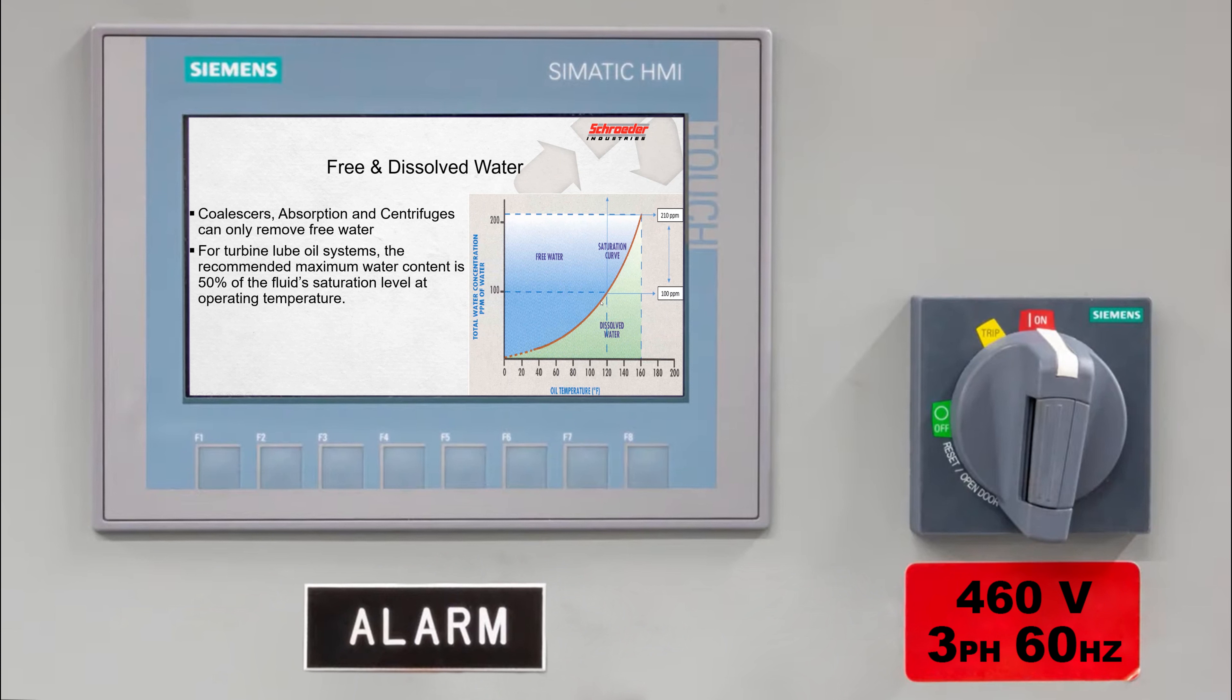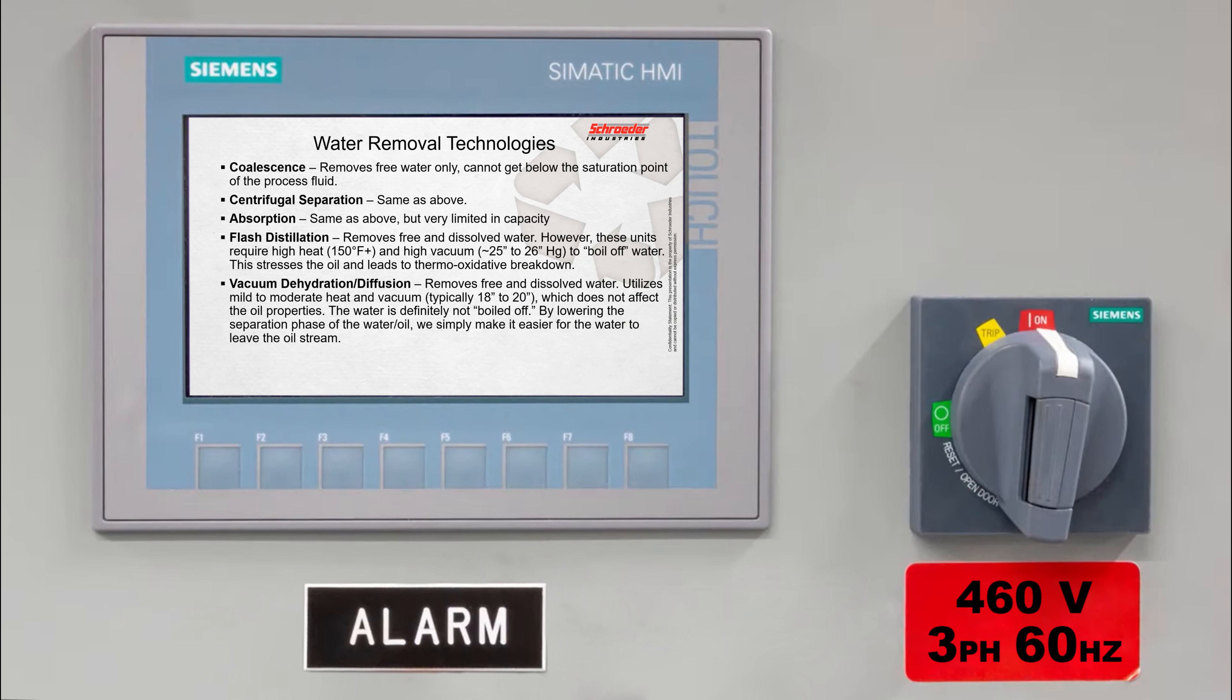The different technologies that are involved for water removal: you got the coalescers, they're going to remove free water only, but they're not going to get it below the saturation point of the fluid. Somewhat cost effective because you don't have to replace them as long as they're kept free of particulate. Centrifugal separation, same as above, very efficient at removing free water, but it's not going to get the absorbed water. Centrifuges do require a tremendous amount of maintenance, power, and they're very expensive. The absorption technology is probably the most cost effective of removing the free water. In a sense it's very cheap, but the elements don't hold a lot of water. You've got to replace a lot of the elements.